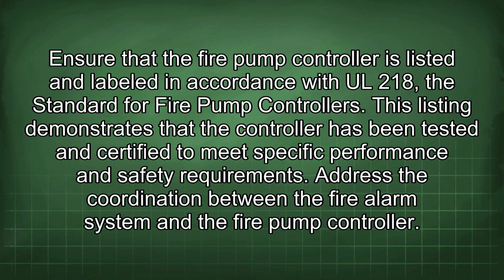Ensure that the fire pump controller is listed and labeled in accordance with UL 218, the standard for fire pump controllers. This listing demonstrates that the controller has been tested and certified to meet specific performance and safety requirements.